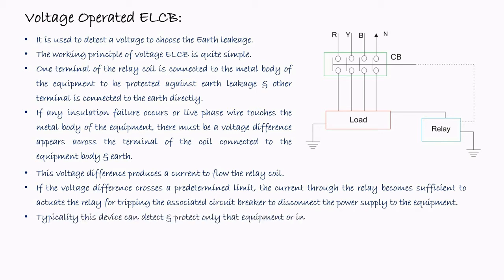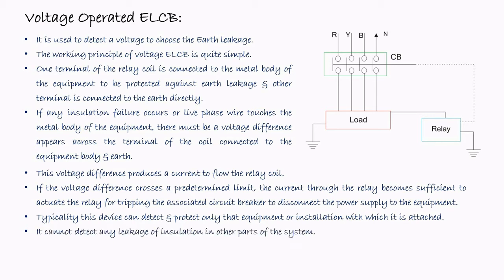Typically, this device can detect and protect only the equipment or installation with which it is attached. That means the voltage operated ELCB is connected to a particular equipment, and then it will protect that particular equipment only, not the entire electrical circuit. So it cannot detect any leakage of the insulation in other parts of the electrical system.